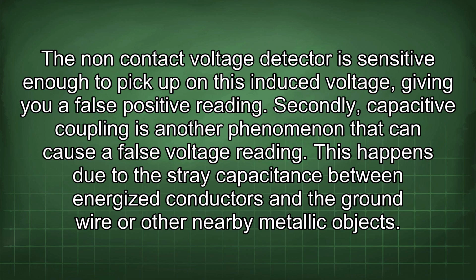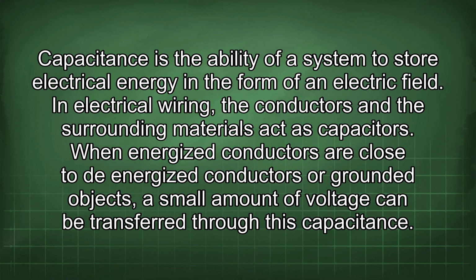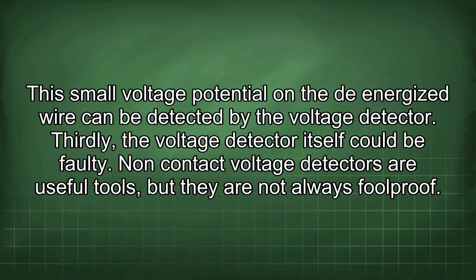Secondly, capacitive coupling is another phenomenon that can cause a false voltage reading. This happens due to the stray capacitance between energized conductors and the ground wire or other nearby metallic object. Capacitance is the ability of a system to store electrical energy in the form of an electric field. In electrical wiring, the conductors and the surrounding materials act as capacitors. When energized conductors are close to de-energized conductors or grounded objects, a small amount of voltage can be transferred through this capacitance. This small voltage potential on the de-energized wire can be detected by the voltage detector.